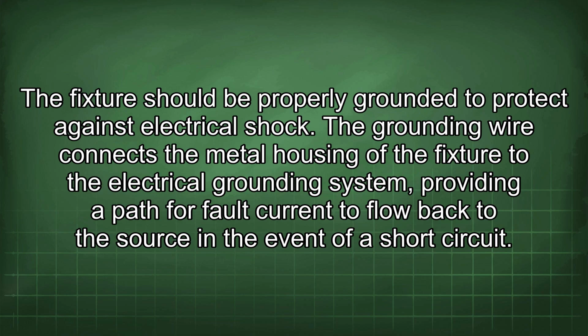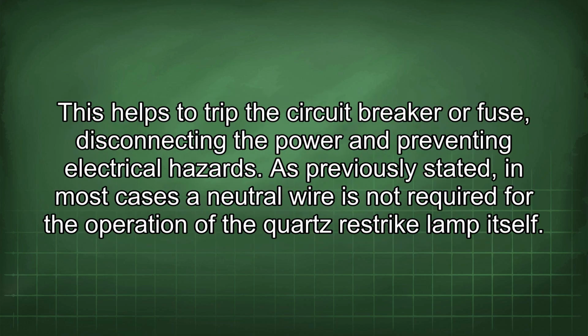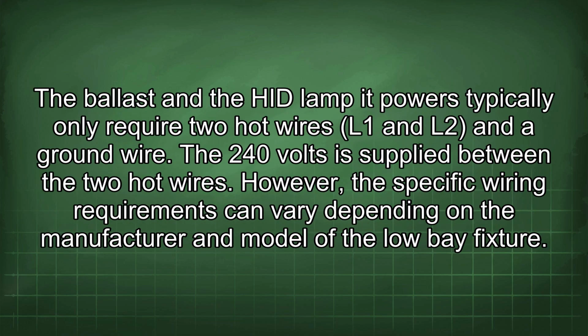The grounding wire connects the metal housing of the fixture to the electrical grounding system, providing a path for fault current to flow back to the source in the event of a short circuit. This helps to trip the circuit breaker or fuse, disconnecting the power and preventing electrical hazards. As previously stated, in most cases a neutral wire is not required for the operation of the quartz restrike lamp itself. The ballast and the HID lamp it powers typically only require two hot wires, L1 and L2, and a ground wire. The 240 volts is supplied between the two hot wires.